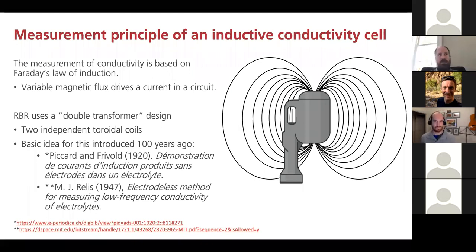So if you ever want to take a drift measurement, for instance, of an inductive cell, simply remove the water. That sounds like it might be tricky, but actually if you're on an Argo float, you just go to the surface. And if you measure at the surface, it doesn't matter if the cell is wet, as long as there is not a single conductive layer all the way around the cell. If that's the case, then you will get a 0 conductivity measurement, and you can assess for yourself any drift that you suspect will be occurring.